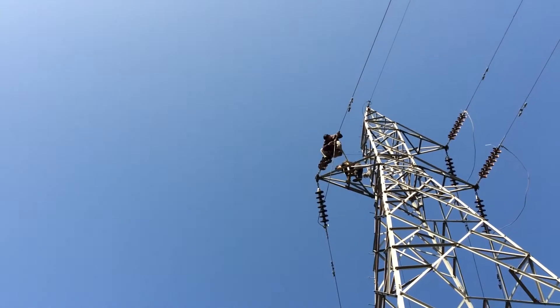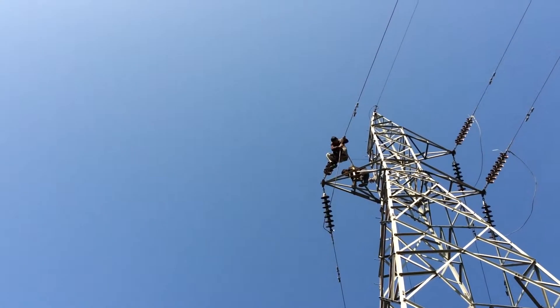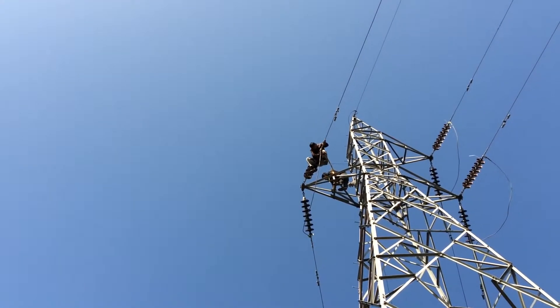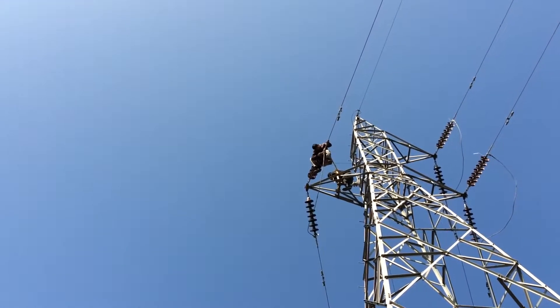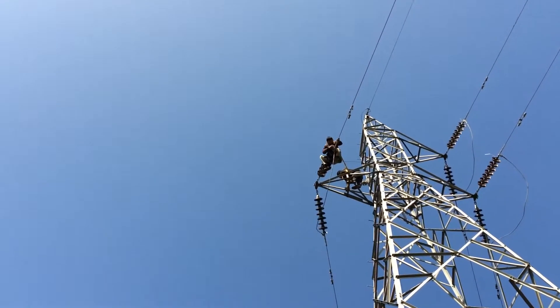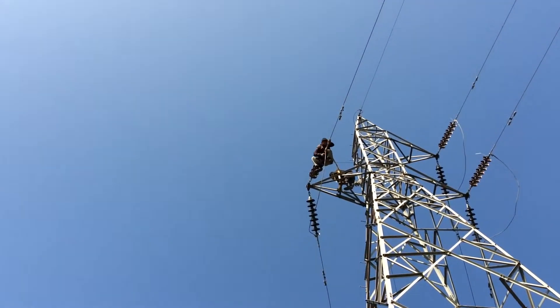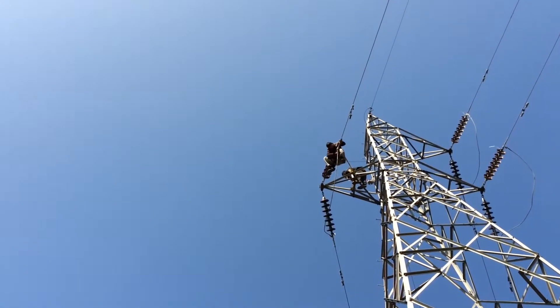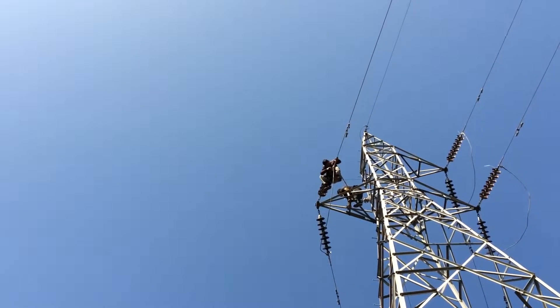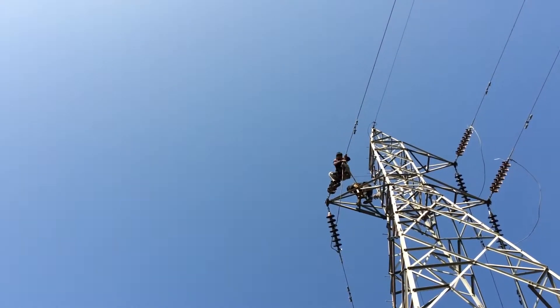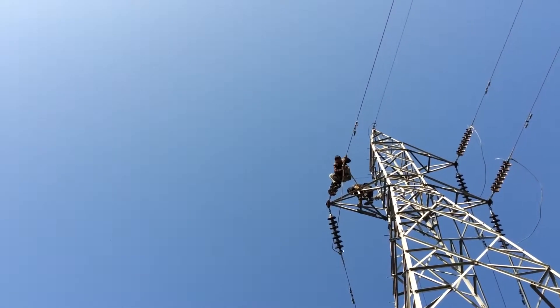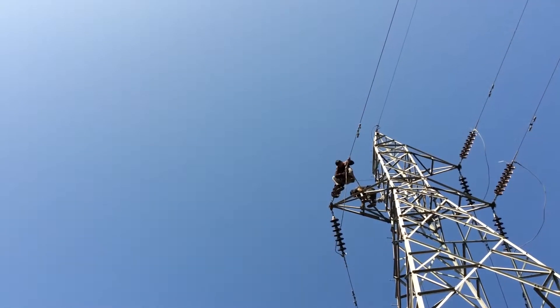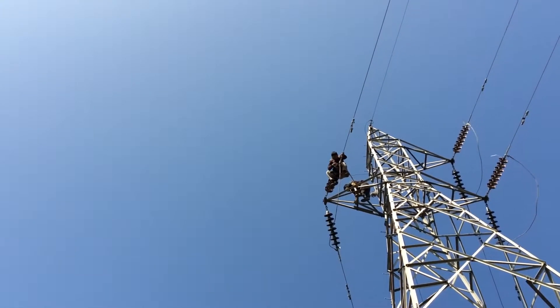There was a problem with the jumpers in almost all the towers. We couldn't find out why the jumpers were being snapped out, so what we are doing is binding up and overlapping the conductor jumpers.